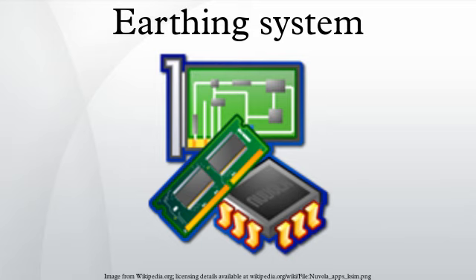The second letter indicates the connection between earth and the electrical device being supplied. T: a direct connection of a point with earth. N: a direct connection to neutral at the origin of installation, which is connected to the earth. TN networks. In a TN earthing system, one of the points in the generator or transformer is connected with earth, usually the star point in a three-phase system. The body of the electrical device is connected with earth via this earth connection at the transformer.